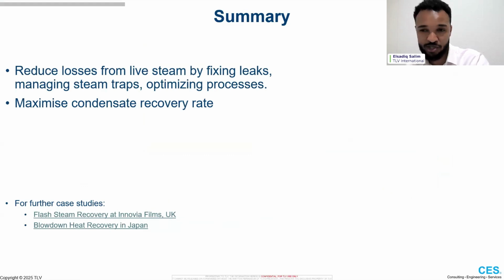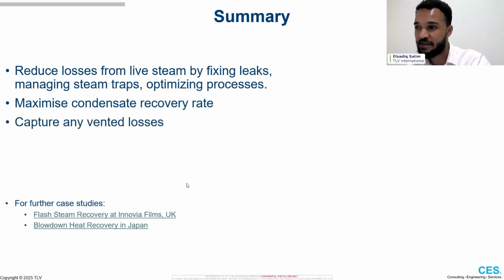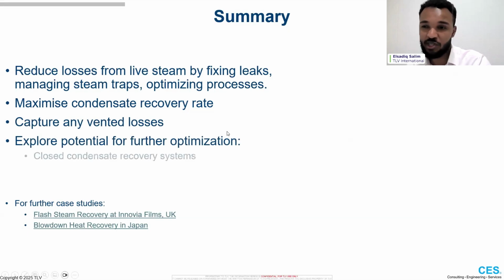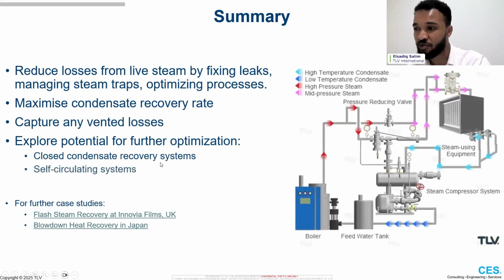As mentioned, reducing losses can come from the live steam system or the condensate system. Always start by trying to maximize your condensate recovery rate before recovering the further losses. Vented losses can be recovered, and there's also always potential for further optimization if you've done those first 3 points, whether it's closed condensate recovery systems or self-circulating systems. We've got a little diagram there that you can peruse at your time.